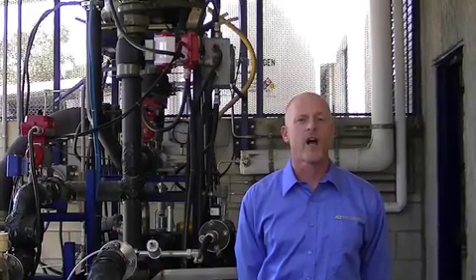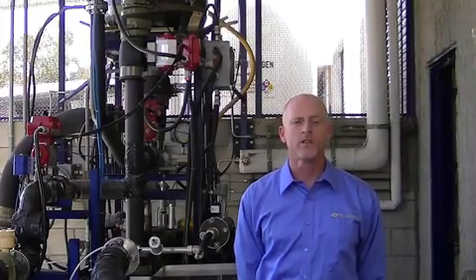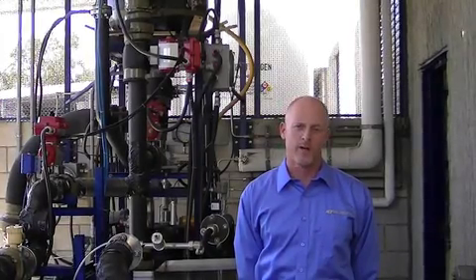This fuel flow test stand was designed primarily for the aerospace division to calibrate liquid flow meters in hydrocarbons, jet fuels, and water ethylene glycol blends. The stand uses two NIST traceable Coriolis meters for extremely high accuracy. With this stand, we can calibrate in virtually any mixed liquid composition.